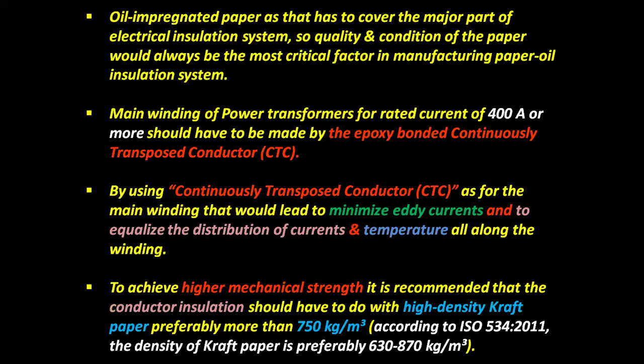Oil impregnated paper covers the major part of the electrical insulation system, so the quality and condition of the paper is always the most critical factor in manufacturing the paper oil insulation system. The main winding of power transformers for rated current of 400 ampere or more should be made of epoxy bonded continuously transposed conductor.